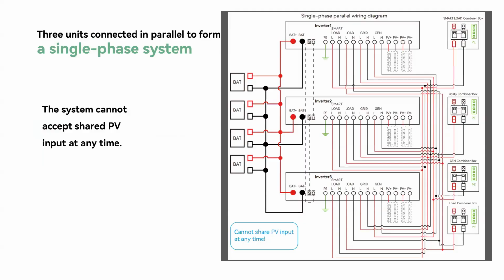Okay, now let's go to the parallel connection. We support both single and three-phase parallel systems, and in all of these we support a shared battery bank. As you can see here, we can connect all the batteries so that all of the inverters can share one battery bank for better energy management. And we have to make sure that each inverter connects to its own separate solar panels. The system cannot accept a shared PV input at any time. It will cause damage to the inverters.